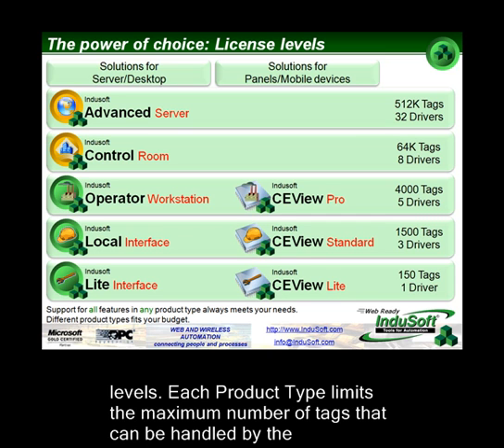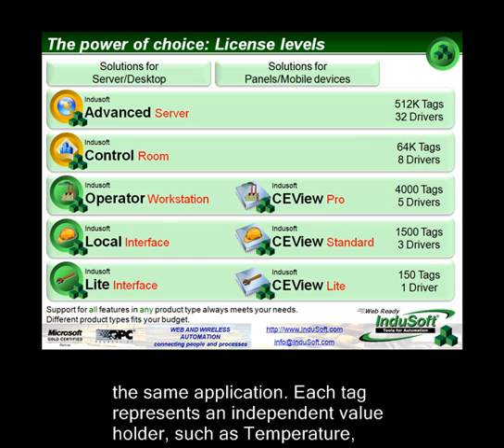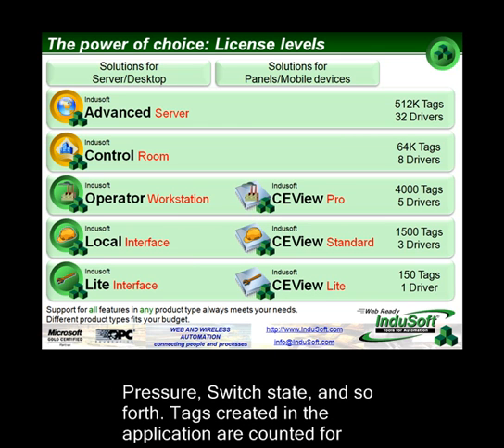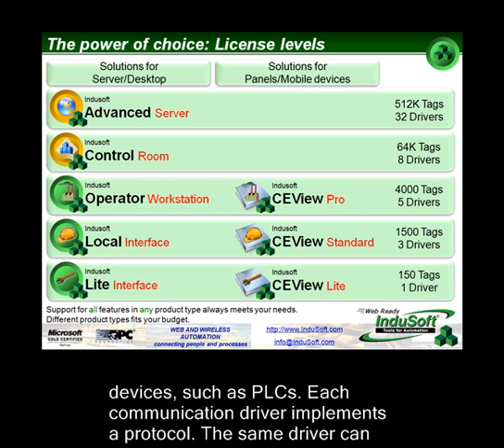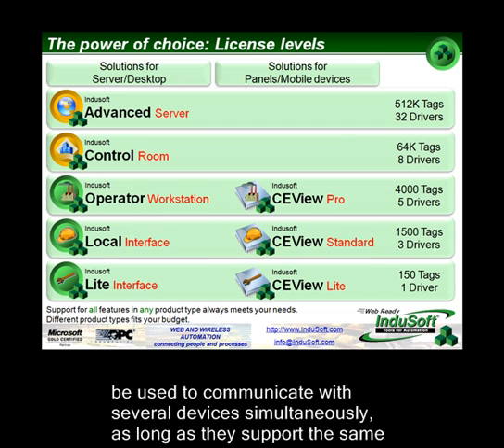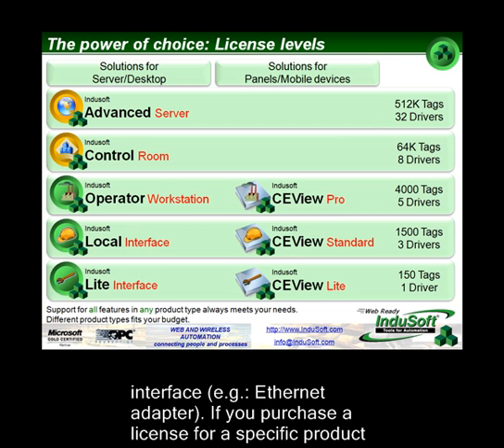This chart represents the difference between the product types, which are the license levels. Each product type limits the maximum number of tags that can be handled by the application, and the maximum number of communication drivers that can run simultaneously for the same application. Each tag represents an independent value holder, such as temperature, pressure, switch state, and so forth. Tags created in the application are accounted for licensing purposes, regardless of whether they are linked to physical addresses of remote devices such as PLCs. Each communication driver implements a protocol and can communicate with several devices simultaneously, as long as they support the same protocol and are connected through the same physical interface, such as an Ethernet adapter.